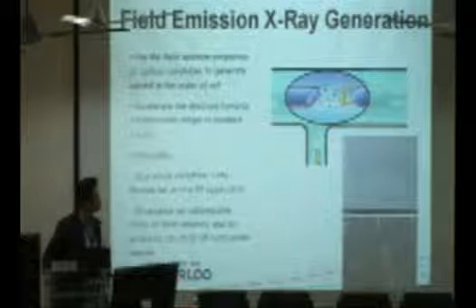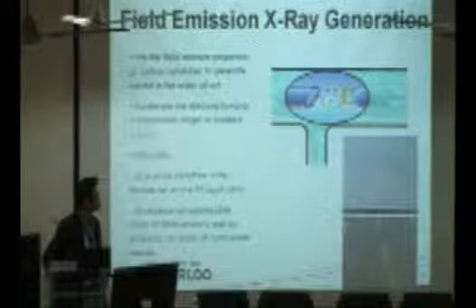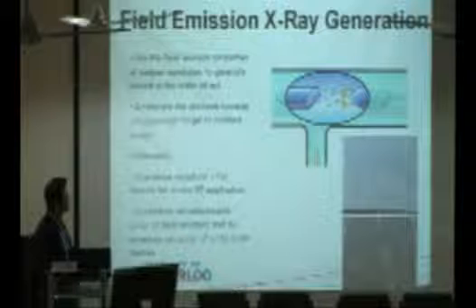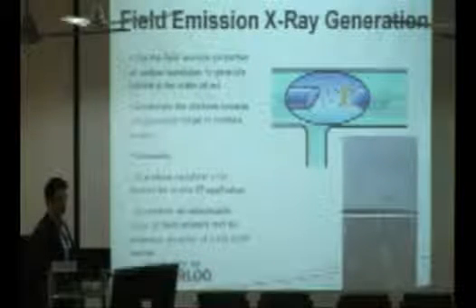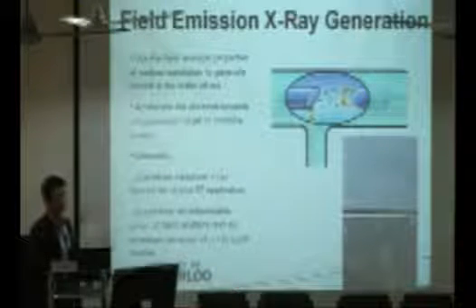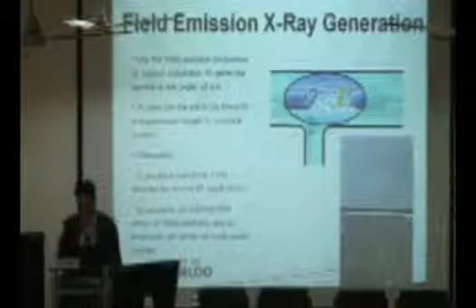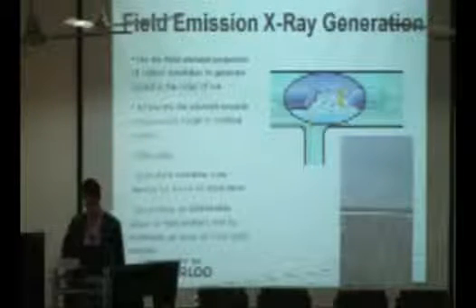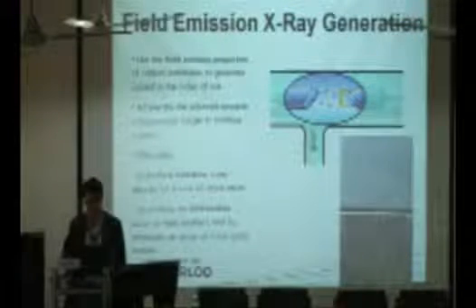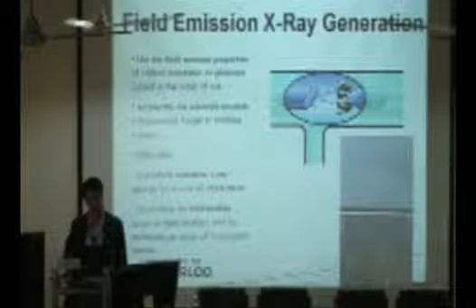Now, I did say that in order to generate X-rays, we need access to free-flowing electrons. So if we were to have a material that could generate electrons, not by thermionic emission, but by field emission, then we could take away the metal filament and replace that with this magic material. Now, it turns out that carbon nanotube is such a material. So what we want to do is to replace the metal filament with an array of carbon nanotubes.